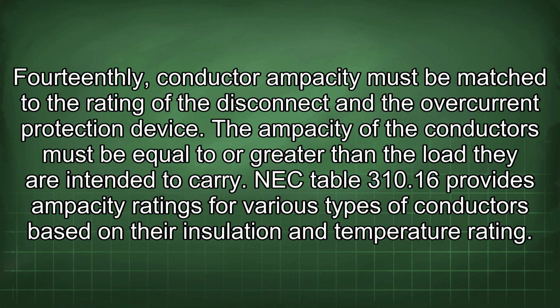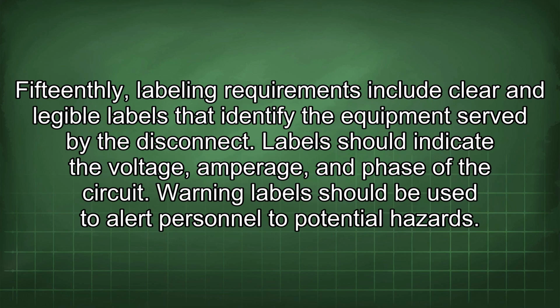The ampacity of the conductors must be equal to or greater than the load they are intended to carry. NEC Table 310.16 provides ampacity ratings for various types of conductors based on their insulation and temperature rating. 15thly, labeling requirements include clear and legible labels that identify the equipment served by the disconnect. Labels should indicate the voltage, amperage, and phase of the circuit. Warning labels should be used to alert personnel to potential hazards.